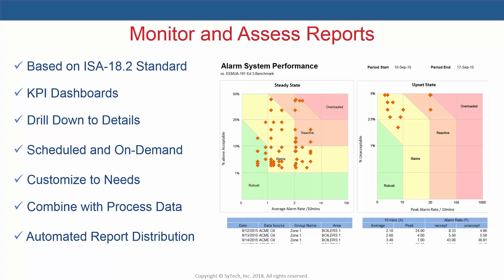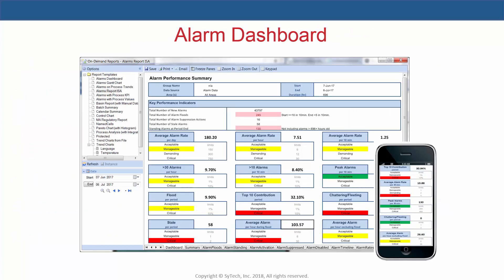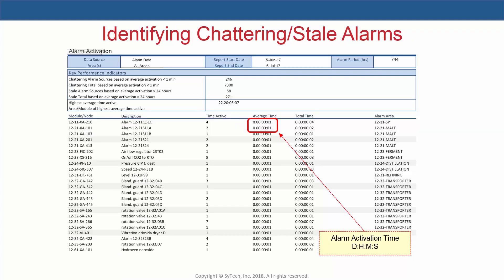Now let's take a look at some example reports. This alarm dashboard report displays ISA 18.2 performance KPIs with an evaluation rating for each. It's easily published to web browsers and mobile devices and is backed up by detailed analysis reports, such as one which helps identify chattering and stale alarms, or alarms with extremely short and long activation times. These alarms both distract operators and can skew the results of assessment reports.